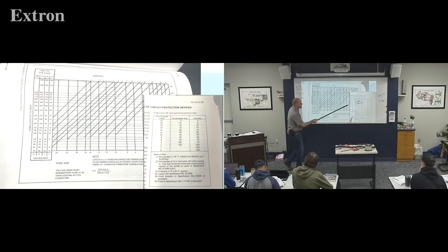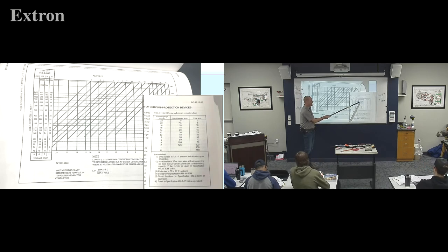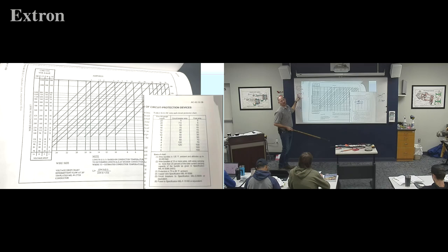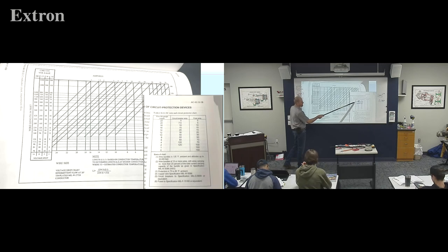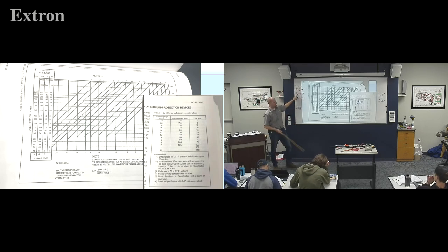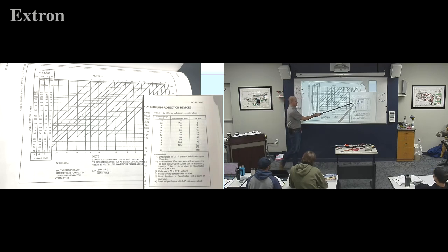Ultimately this chart is supposed to be here to decide our breaker size, but we always have to go double check and make sure. In this Concorde situation, if I said, oh yeah, hindsight, I need a circuit breaker, I just ran an 18 gauge wire, what size circuit breaker do I need? Well, if I had a 10 amp motor and I stuck in a 7.5 amp circuit breaker, it's going to pop. So you would still put a 10 amp circuit breaker in there, but I bump the wire size up from 20 to 18.